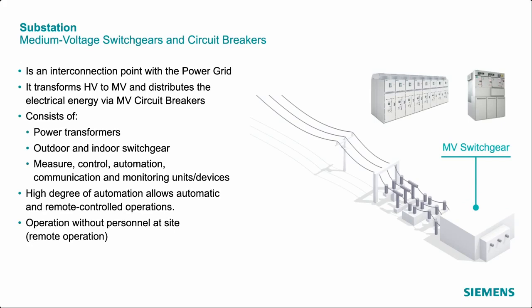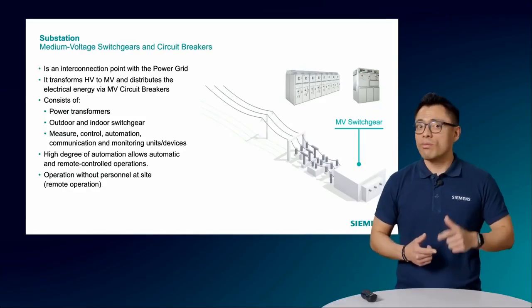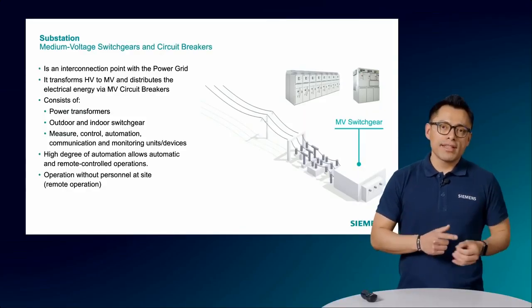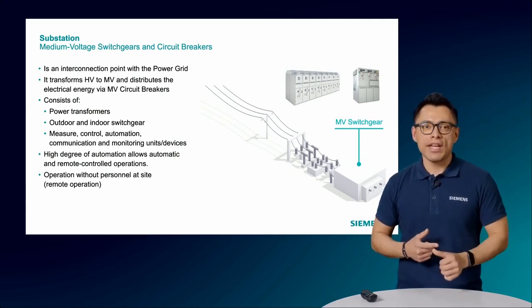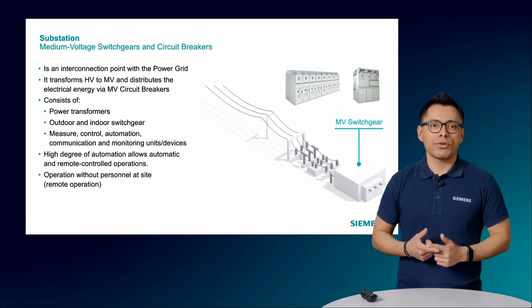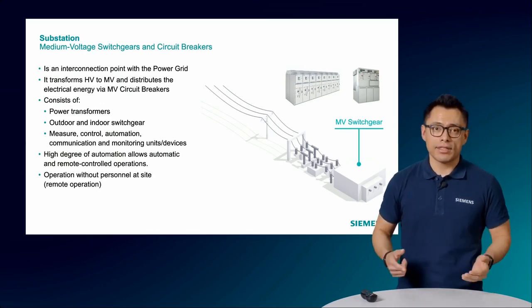Commonly, high voltage comes to the substations via overhead lines, while medium voltage is handled inside the substation via medium voltage switchgears and medium voltage circuit breakers. Therefore, substations consist of power transformers and switchgears, which can also be indoor or outdoor. There are some other components related to other critical functionalities like measurement, control, automation, communication, or monitoring. These other components enhance the operation as they can provide a high degree of digitalization, automation, and remote control, which means site operation without personnel.